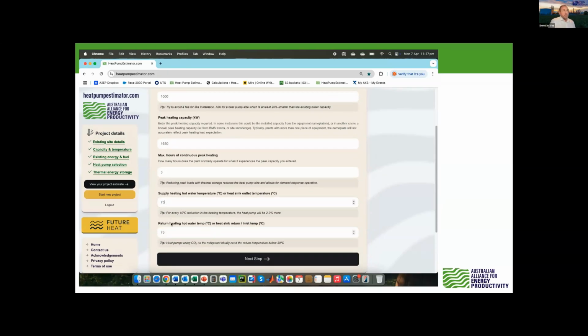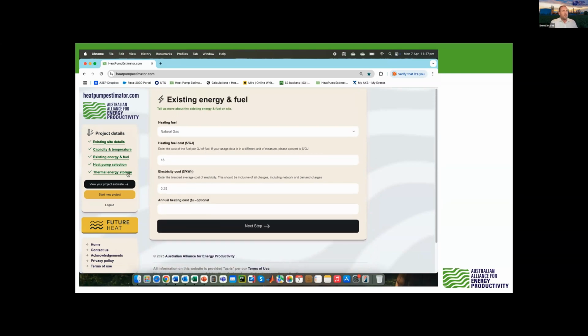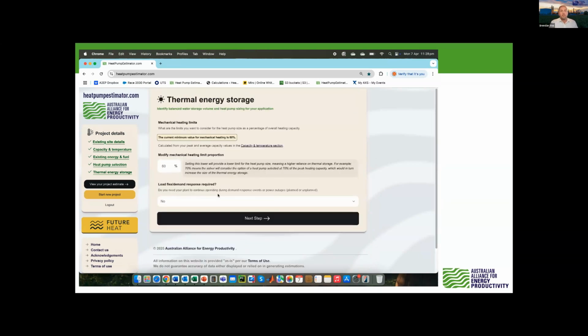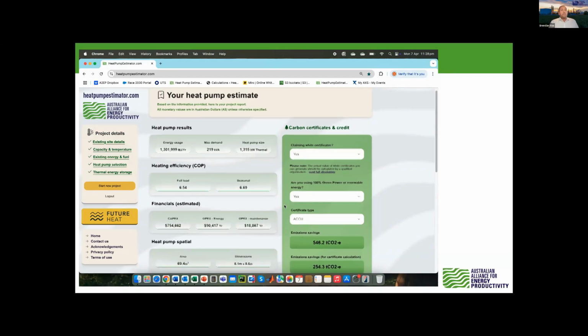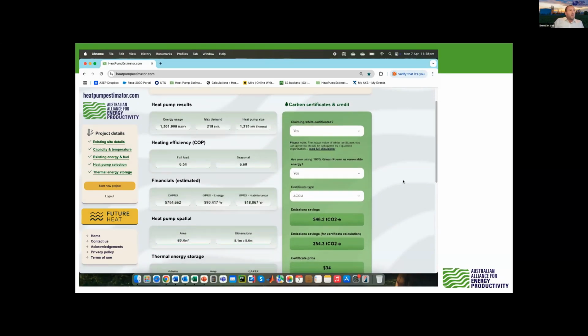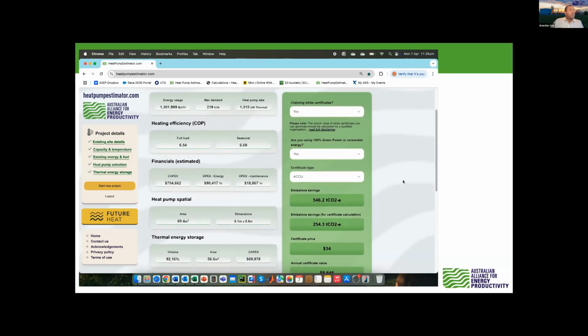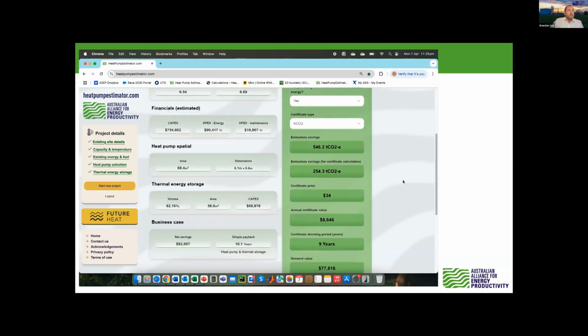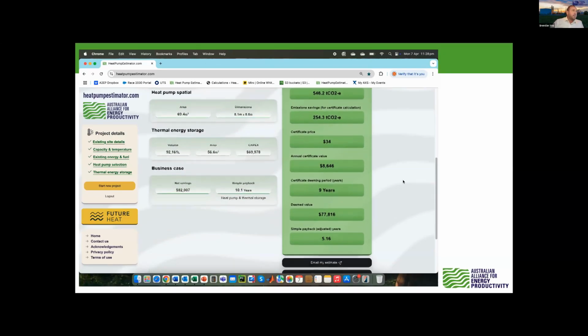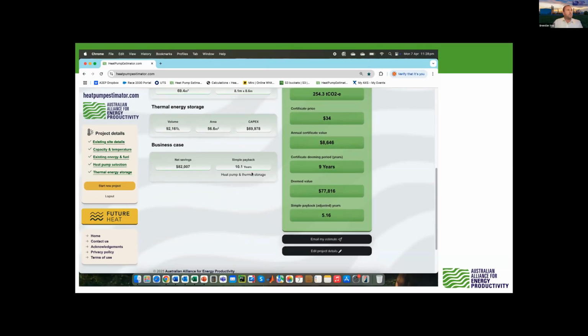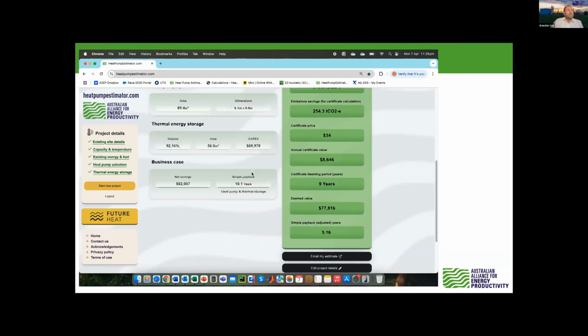Now I'm just going to quickly, just as an example, wind it down to 75. And we're going to go back through the steps, which will all be the same. I'm not going to change anything else. And now if you have a look, my full load COP and my seasonal COP have improved. My heat pump size didn't change, but my payback is now 10 years. So Jared's logic before, that it gets better as you decrease that temperature, does show that.